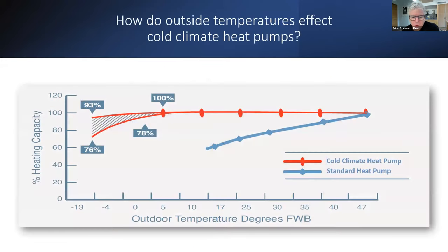Because I think that slide is really helpful. In the standard heat pump line, what that's saying is that as the temperature gets colder, the heat pump is able to produce less heat. And that can be a real problem if your home needs more than those numbers of BTUs that it's putting out as the temperature gets colder. Because if you had a line that showed what the house needs, it would be a line angling up from the lower left to the lower right, going up, right? Basically, because it needs more as the temperature drops. So, can you just chat on that a little bit?